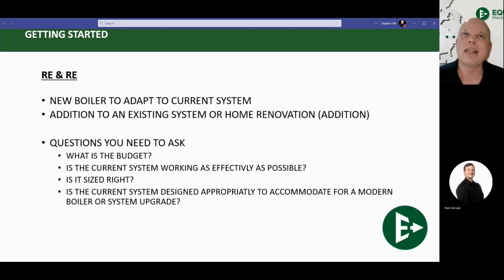But a couple things that you can tell without doing a heat loss: you can usually talk to the homeowner. Did they have a lot of short cycling? Did they have a lot of failures? Did they go through igniters quickly? That's a good sign that the system is oversized. If the system had a hard time keeping up in the winter, if they ran out of hot water with an indirect water heater, that's a sign that the system is going to be undersized. So that's a question you're going to want to make sure that you have isolated and identified, because again, this is the time to get that sort of thing addressed moving forward.